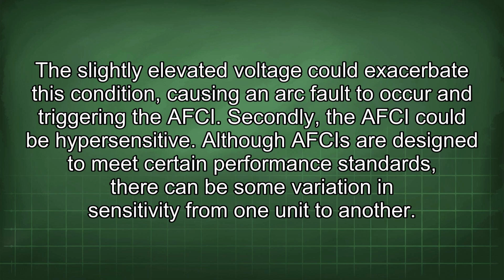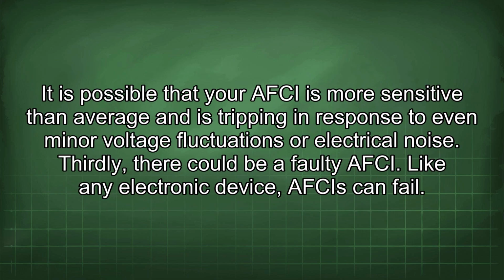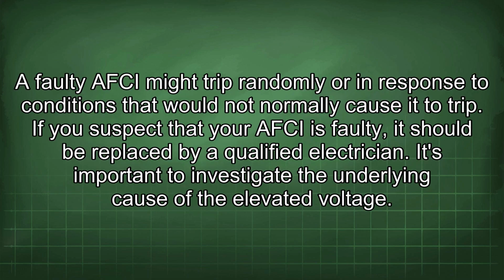Secondly, the AFCI could be hypersensitive. Although AFCIs are designed to meet certain performance standards, there can be some variation in sensitivity from one unit to another. It is possible that your AFCI is more sensitive than average and is tripping in response to even minor voltage fluctuations or electrical noise. Thirdly, there could be a faulty AFCI. Like any electronic device, AFCIs can fail. A faulty AFCI might trip randomly or in response to conditions that would not normally cause it to trip. If you suspect that your AFCI is faulty, it should be replaced by a qualified electrician.